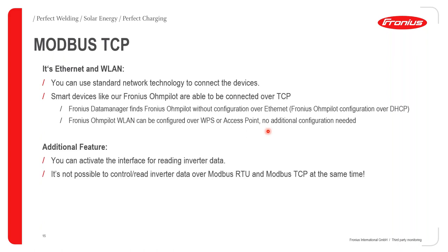The Fronius wireless LAN can be configured over WPS or the access point function. No additional configuration is needed, and you can activate the interface for reading inverter data. Note that it is not possible to control and read inverter data over Modbus RTU and Modbus TCP at the same time — you must select one channel only.